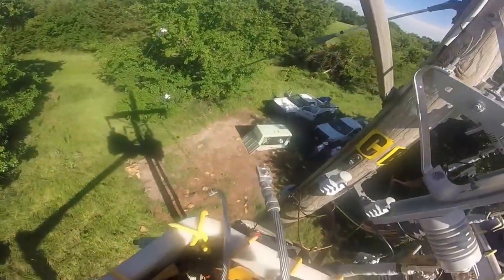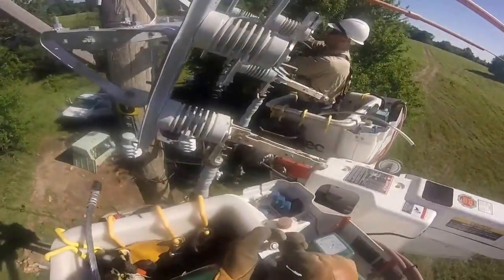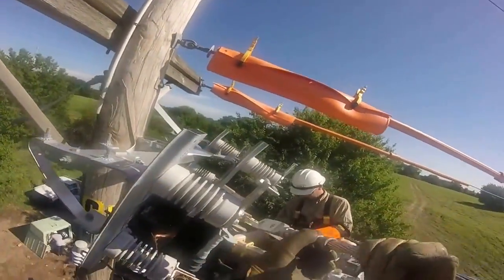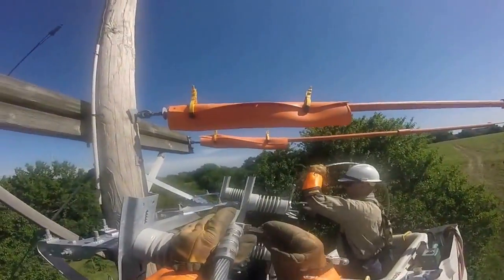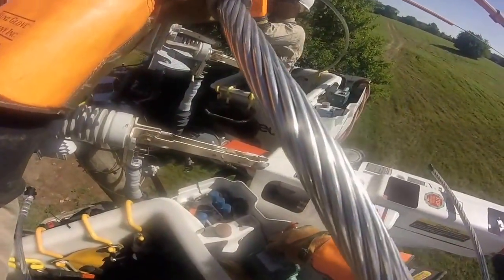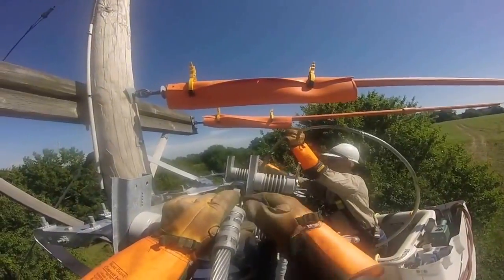He's going to grab what's called a jumper, or a tap, and this makes the connection between the switch and the line coming in. You see here he's going to attach that jumper to this switch plate. Notice how he's working on the middle phase — they always try to keep outside the phase — and also notice the line protectors and the gloves, as these are energized lines.